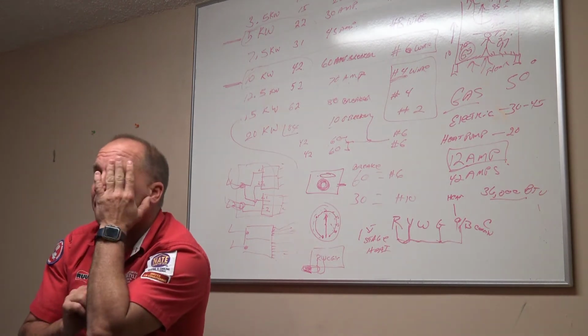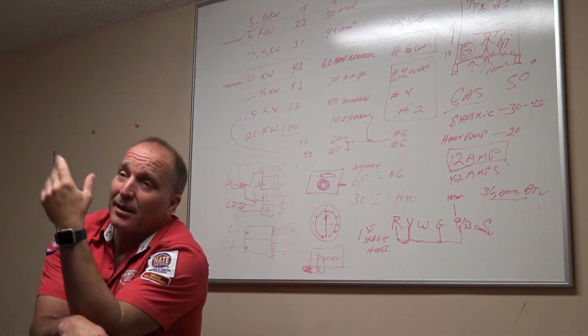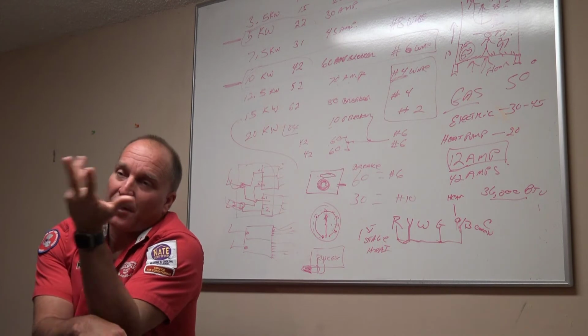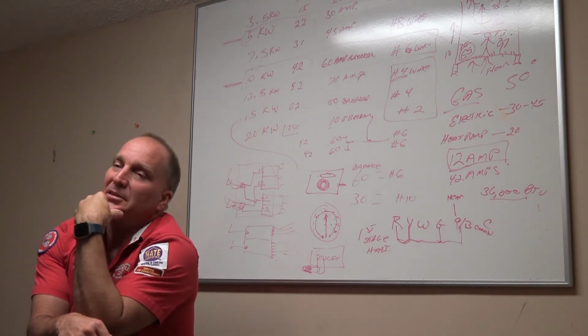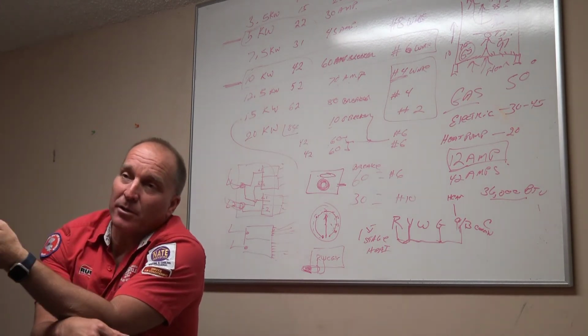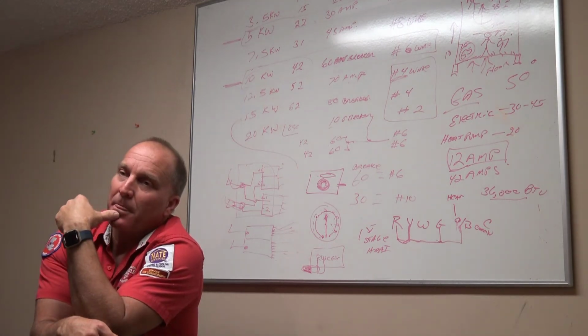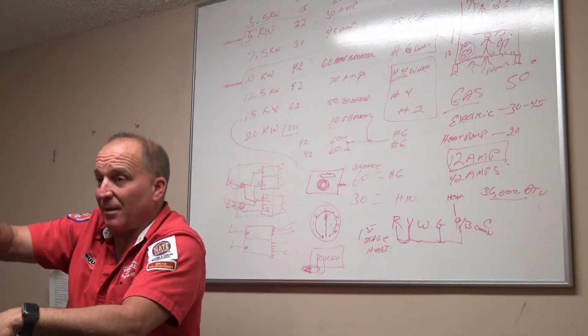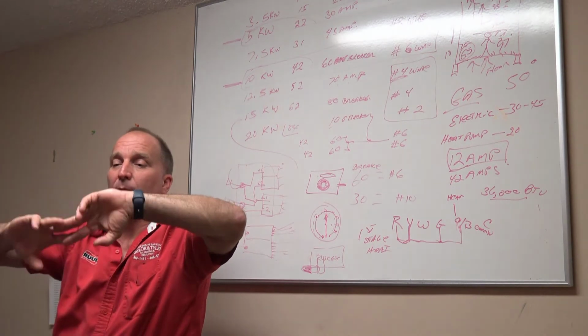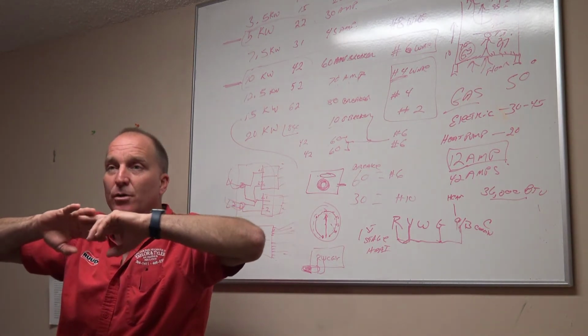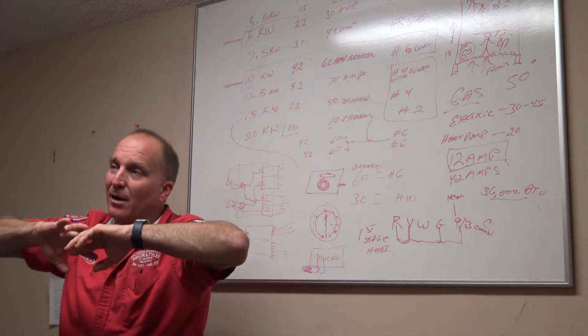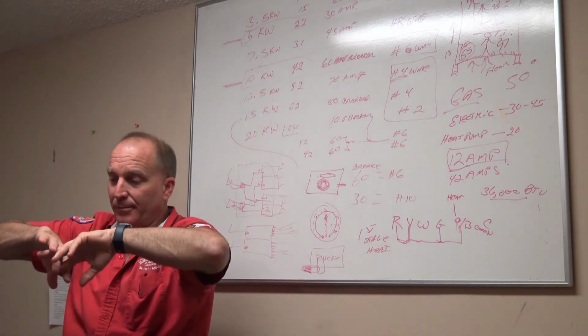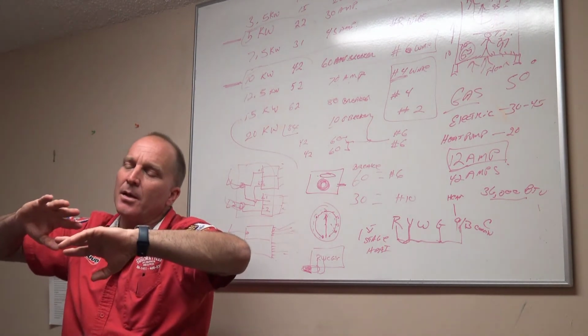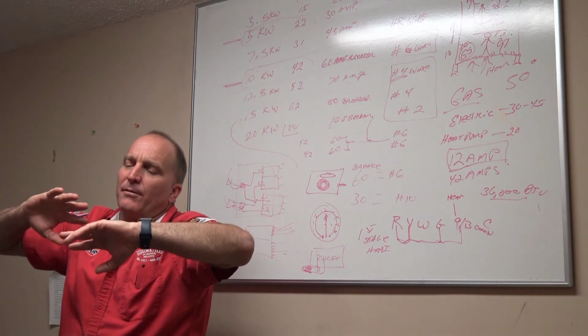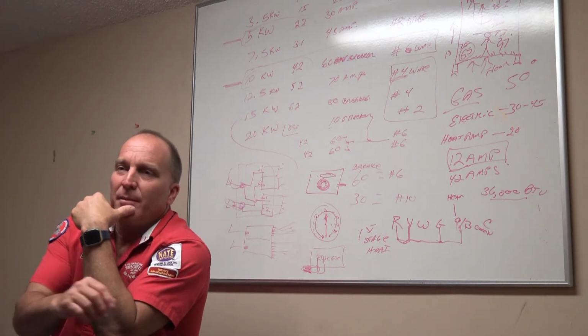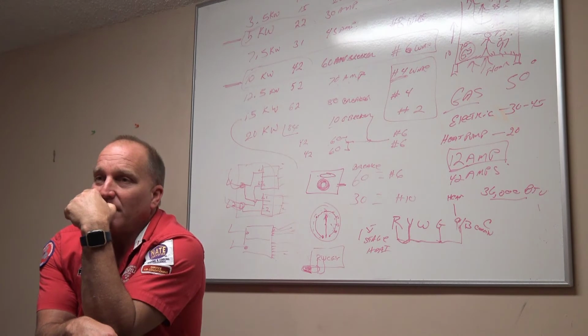Now think about this. I've got a main electrical panel with a 60 amp breaker, call it 10 kW heat, and that breaker is all chewed up. I have to replace it. But if the terminal bar I'm plugging it into is all chewed up and beat down, like it's been eaten by a dinosaur or something, if I put a new breaker in there, is it going to do the same thing? Yeah, it's a bad connection.